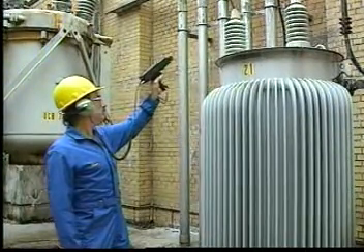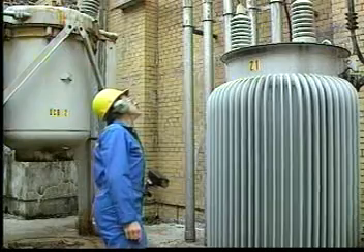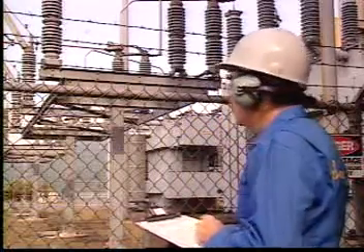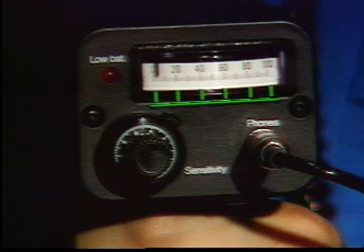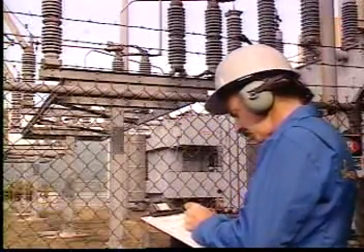Listen for differences as you visually inspect them and make notes for future comparisons. You may also use your own senses to detect changes — you may be able to smell ozone or see discoloration. Monitor your equipment regularly by listening to everything and record the results. Although the log mode is used for real-time scanning to pinpoint a problem site, we recommend switching to the Lin mode for a steady response when monitoring. Note whether you heard arcing, tracking, or corona, and include the location, temperature, and relative humidity at the time of testing.